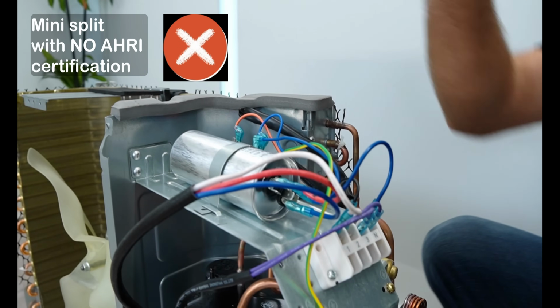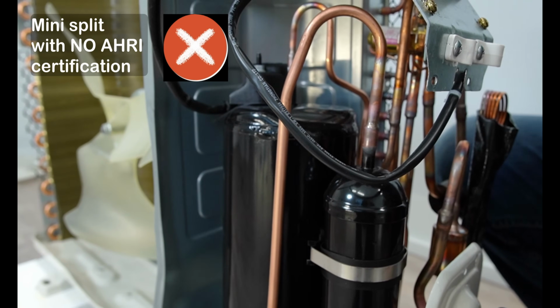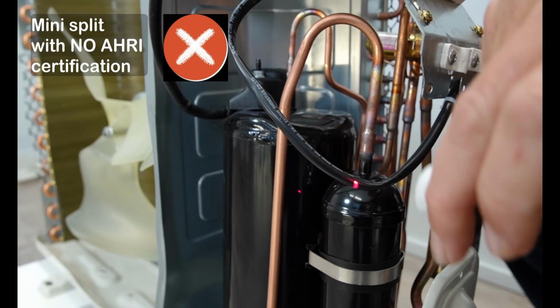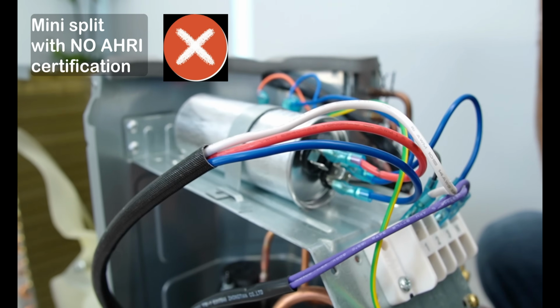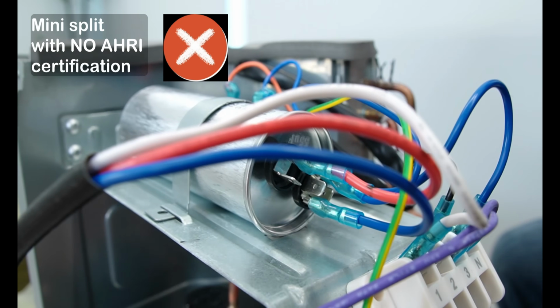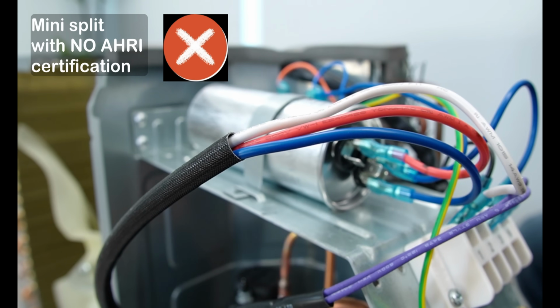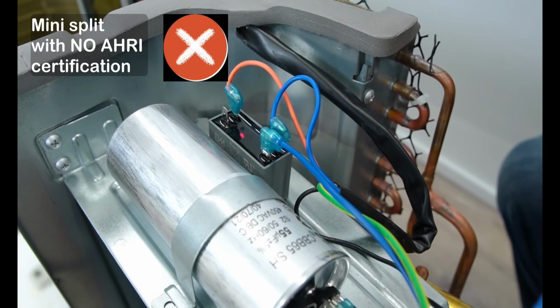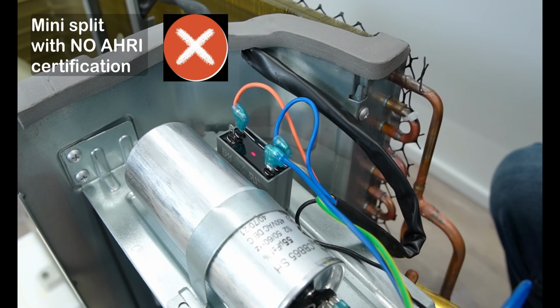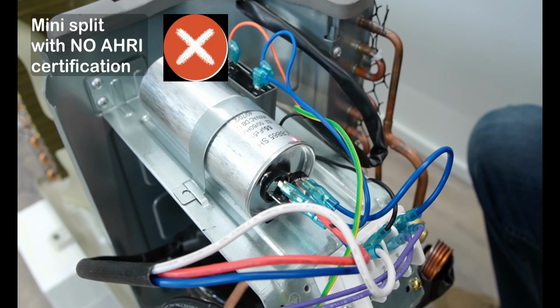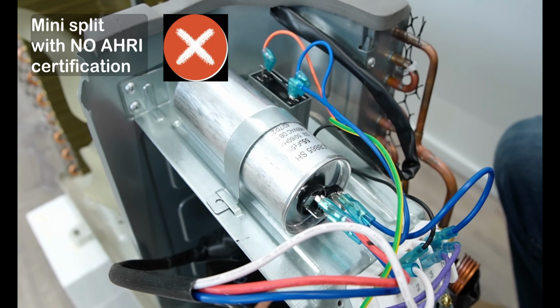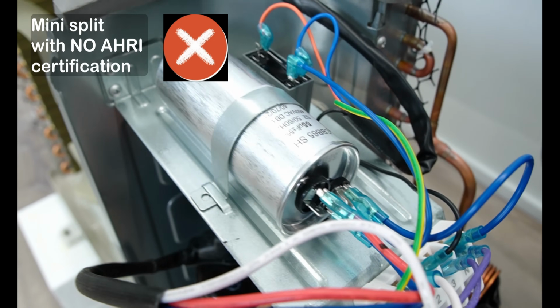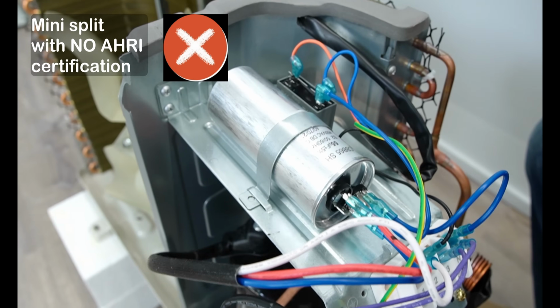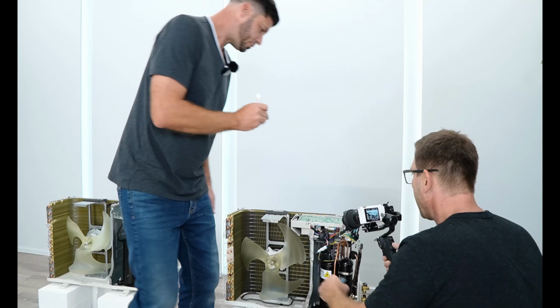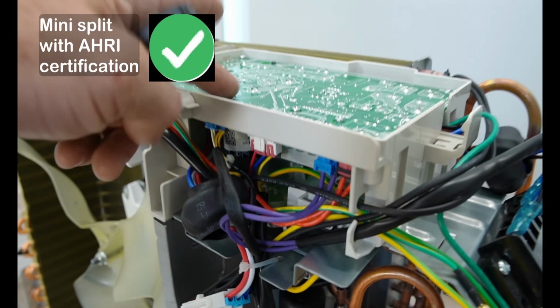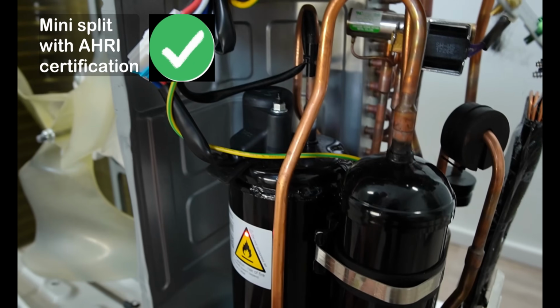Nope, no inverter board. We have a single stage compressor. That's bulky, that's huge. Yeah, that's a big bulky compressor. Single stage compressor, paired with a 55 microfarad polypropylene capacitor. No inverter board. Now this has a 5 microfarad capacitor for the fan motor. They could have easily just put a dual capacitor on here. Not sure why they did that. Yeah, they had to complicate this. Why couldn't they just do a 55/5 dual run capacitor? Yeah, that doesn't make sense. And again, versus this one, which has the inverter board and a DC compressor.